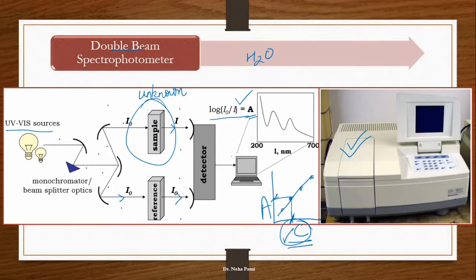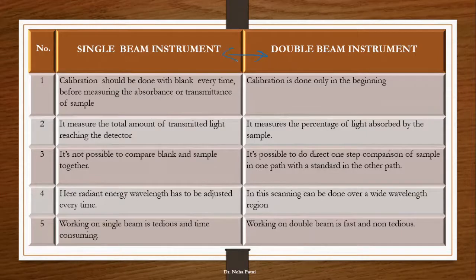If you calculate the absorbance using the detector and plot it on the graph, after extrapolating you will know the concentration. That is a very important and unique feature. Now, how are we going to differentiate or compare? It is very simple - in single beam, the calibration has to be done with blank every time before measuring the absorbance so that the blank solution won't interfere. While in double beam, the calibration is done only in the beginning and we take both beams together.